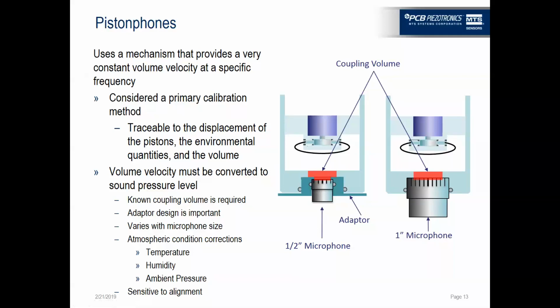A piston phone generates a known volume velocity, which needs to be converted into a sound pressure because that's what a microphone measures. So in order to do that, you need multiple pieces of information. You need to know what the coupling volume is, which is the volume in front of the microphone that's part of not only the grid cap, but also the whole adapter piece that goes with the microphone.